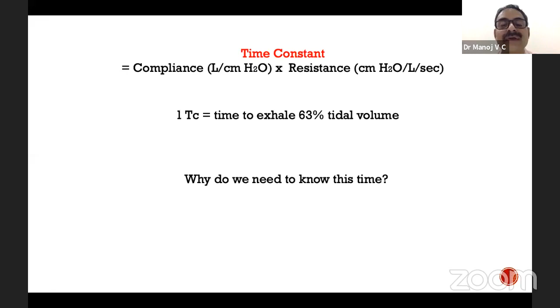So if you want to push in all the air, 5 times the time constant should be the time that you would need to push in air. Pushing in air is the time that you use as inspiratory time. In conventional ventilation, expiration is passive, which means that you don't have control over it. So you control only inspiratory time or respiratory rate, and indirectly control the expiratory time, unlike in high frequency ventilation. So here the inspiratory time should ideally be 5.